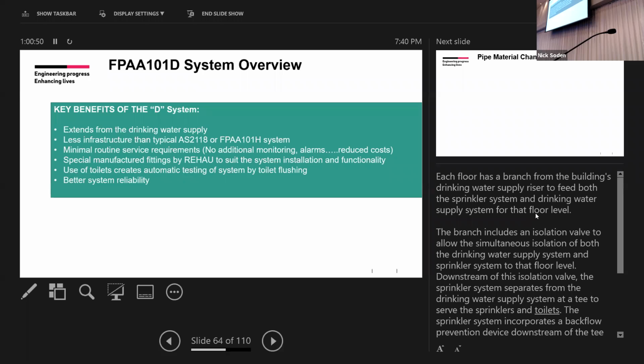And this is where some of the fire engineers have a lot of caution, because they're used to monitoring, they're used to alarms. However, this is one way they can reduce the cost, because the standard, from what we understand as well, was put in place not to save the building, but to save lives. Okay, that's the biggest terminology that we keep getting told on that behalf. So that's why reducing that big infrastructure and alarms and monitoring, they can reduce costs as well. So you're still putting a fire system in, however, it's not a full system.